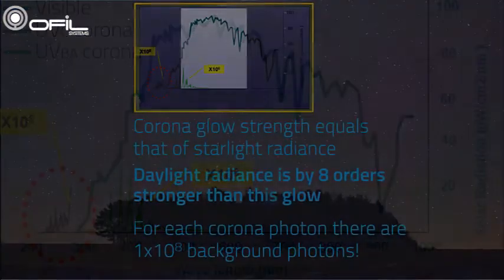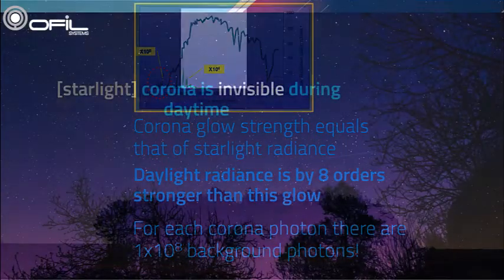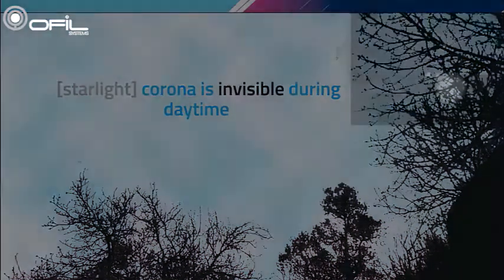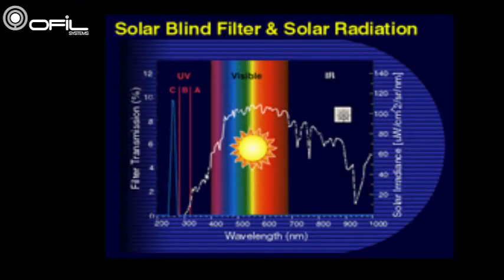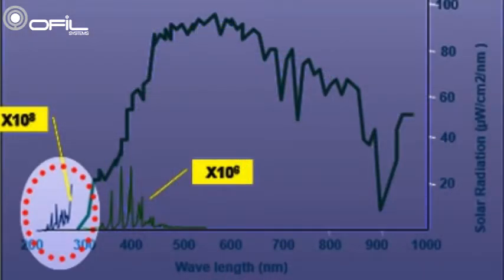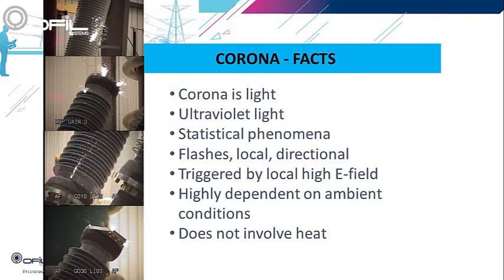The spectral range of corona PD lies between the solar blind UVC and the visible spectral range. The bright daylight radiance is eight orders stronger than that of corona glow and hinders seeing the faint corona PD. This is why corona is invisible during daytime. However, corona emits UV light in the solar blind zone — the dark zone where ozone blocks UV from the Sun — and the DayCor technology enables seeing this solar blind UV, thereby revealing corona.